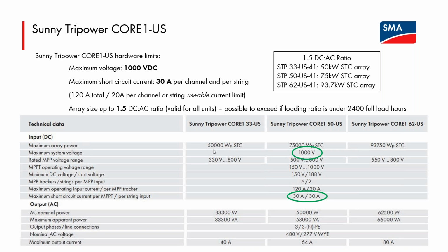the first row of the data sheet shows the maximum DC rating of an array that we at SMA allow you to attach to each of the power classes without any further consultation with SMA. So you can go up to a 1.5 DC to AC ratio on each of the 3 power classes without consulting at all with SMA. So you can see for the 50 kilowatt model, the 50 is the AC power limit coming out of the inverter. So it will never export more than 50 kilowatts AC, but you can attach to it a 75 kilowatt STC rated array, again, provided the 2 values circled in green are always being respected.